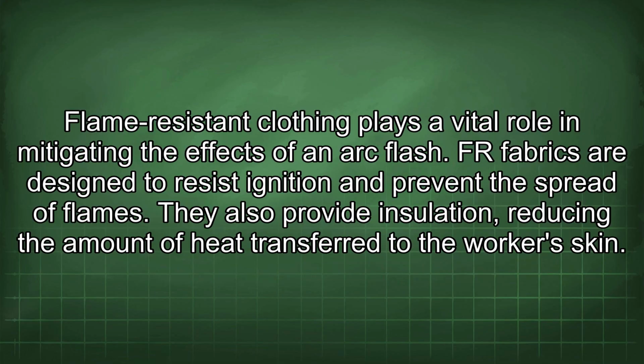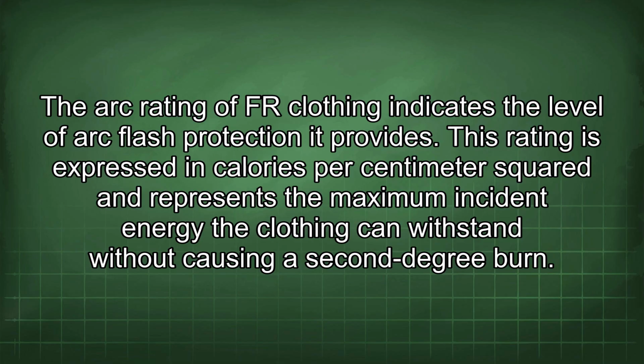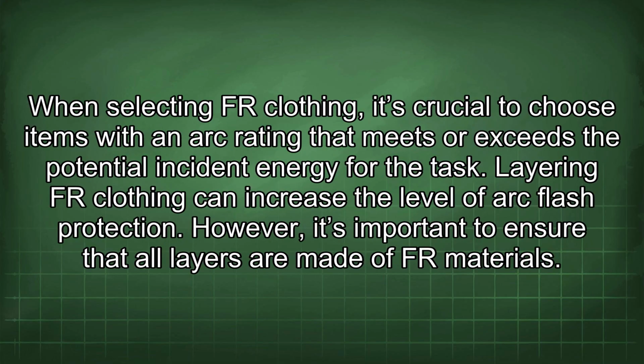Flame-resistant clothing plays a vital role in mitigating the effects of an arc flash. FR fabrics are designed to resist ignition and prevent the spread of flames. They also provide insulation, reducing the amount of heat transferred to the worker's skin. The arc rating of FR clothing indicates the level of arc flash protection it provides. This rating is expressed in calories per centimeter squared and represents the maximum incident energy the clothing can withstand without causing a second-degree burn. When selecting FR clothing, it's crucial to choose items with an arc rating that meets or exceeds the potential incident energy for the task.